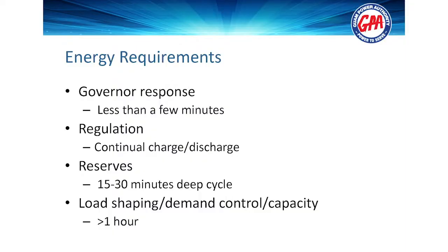Regulation. These are the two issues, and right now, the two opposing technologies within the battery market. Regulation, which is a continual charge and discharge. Whether it's solar or whether it's wind, you'll notice when you start putting that on your system, your frequency is no longer this, it's this. That continual up and down of 60 hertz, going down to 59.6, going up to 60.6, is called regulation. The requirements of that are much different than the next one, the reserves, where you trip a unit and all of a sudden your frequency drops like a rock from 60 down to 59, and your batteries have to give all they have to bring the frequency back to 60 hertz. One's called a deep discharge cycle, the reserve requirement. One's called a continual charge discharge cycle. Those are two different battery technologies.